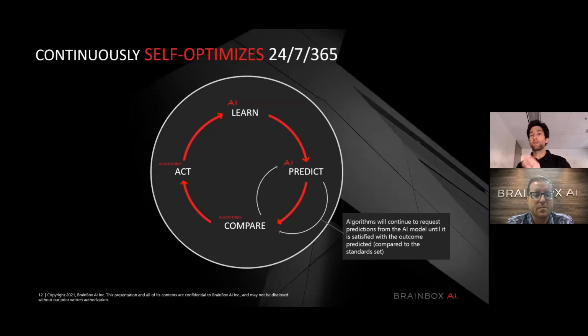And all these inputs get rolled into a model, and from that model, we send our temperature predictions over, and we decide, in this case, when to start equipment or when to stop equipment. So we make a prediction. Based on that prediction, our algorithms will know whether to write to the controller in order to enable our system to start up on morning warm-up or morning cool down, or whether to hold off for a bit longer because we know we'll be able to recover in time and we'll use less energy by doing so.